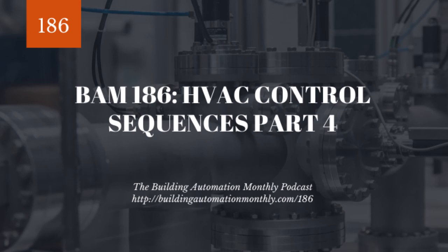Now, it's all well and good to have a damper status, but sometimes those damper statuses can fail. There's a bunch of issues that could potentially occur that could cause us to have no damper open, even though we have status saying it is open. That's why we always typically want to have a low static pressure safety cutoff. And that low static pressure safety cutoff is going to make sure that, hey, if our static starts to drop too low, meaning that we have an issue with our fan and the damper most likely being closed, we then will shut off the fan. So that's kind of our safety there.